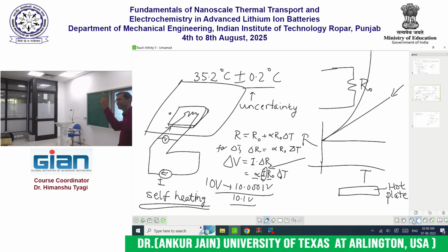Because the manufacturer has calibrated that hot plate against something else in their labs. And how are they confident that they have done it correctly? Because their calibration source has in turn been calibrated against something better. In fact, you can take this chain all the way back to some very well known standards of temperature that NIST, the National Institute of Standards and Technology in the US, maintains.